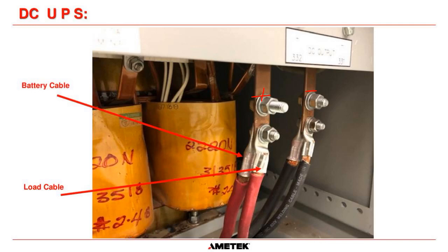And don't get me wrong, this will work absolutely perfectly. In normal operation, this will be fine. But if you have a failure in your charger or in your battery, you are going to have to take a load outage in most circumstances, because you're going to have to disconnect one of these cables. And that means you have to loosen that nut and pull those cables apart, and therefore you will lose the connection between the charger and the load circuits, or the charger and the battery. So it's not a good design.